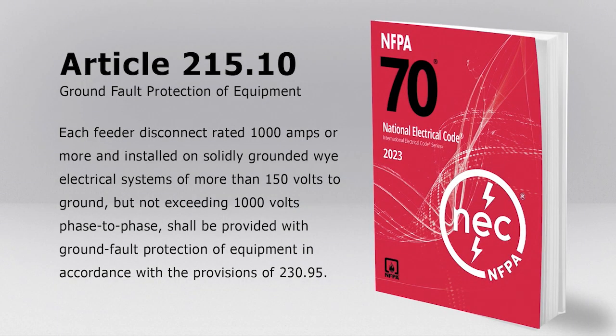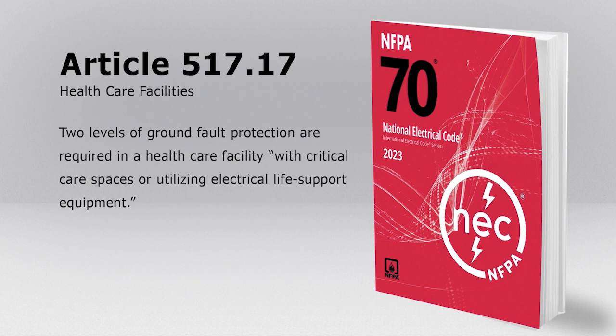And so where in the NEC does it say you have to do that? Well, Article 215.10 talks about ground fault protection of equipment. Each feeder disconnect rated 1,000 amps or more, if it's installed on a solidly grounded Y system, if it's greater than 150 volts to ground, and if it doesn't exceed 1,000 volts phase to phase, so we're talking about low voltage equipment, and it's in accordance with the provisions of Article 230.95. 230.95, we're going to talk about that here in just a minute. And if you operate a healthcare facility, check out Article 517.17 because there's another layer of protection that you've got to have relative to ground fault protection.